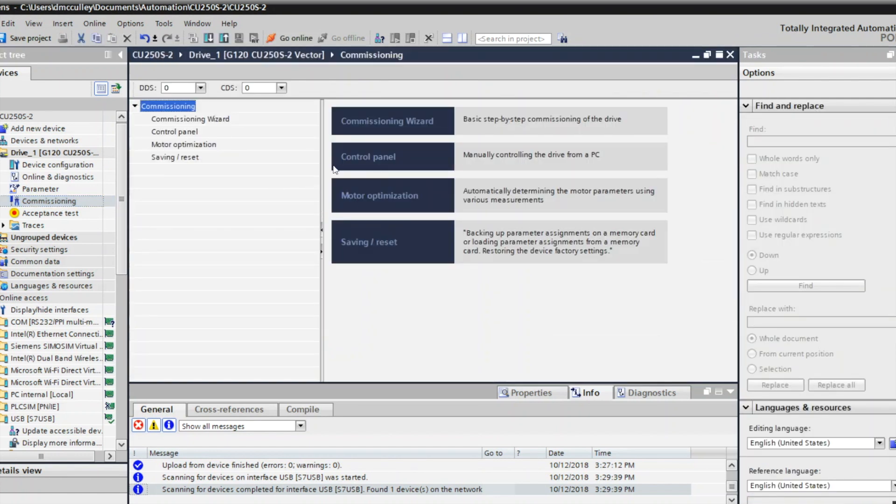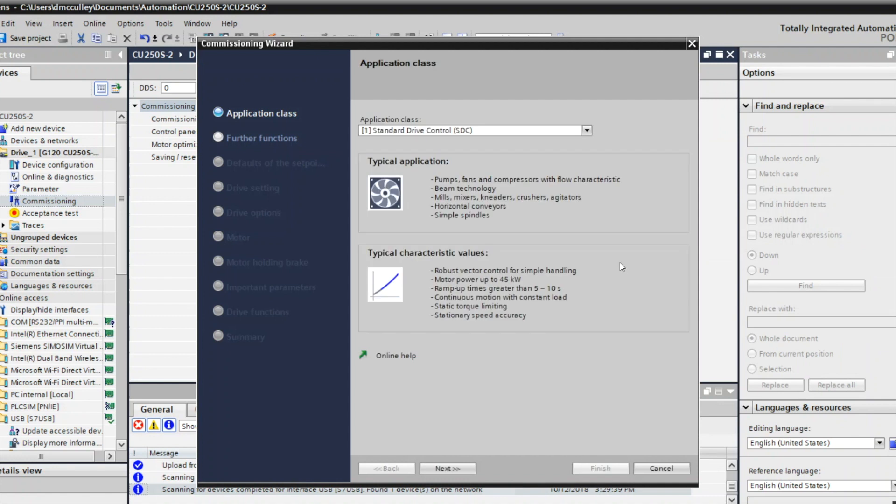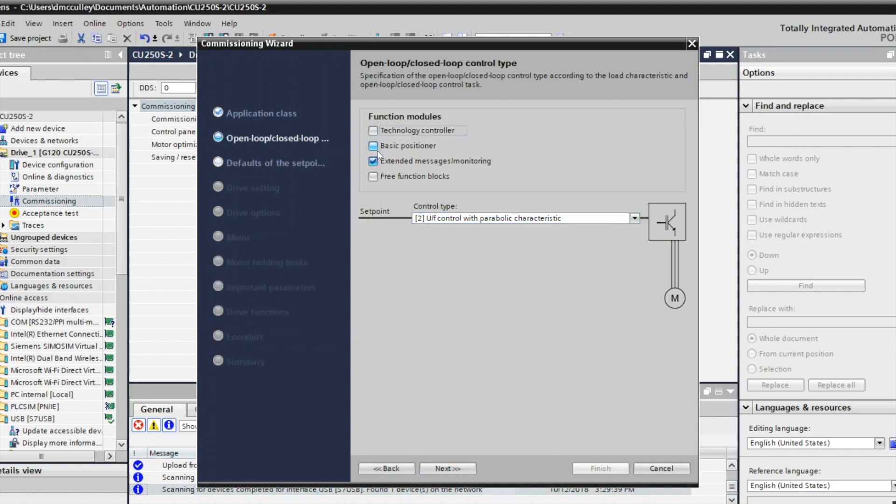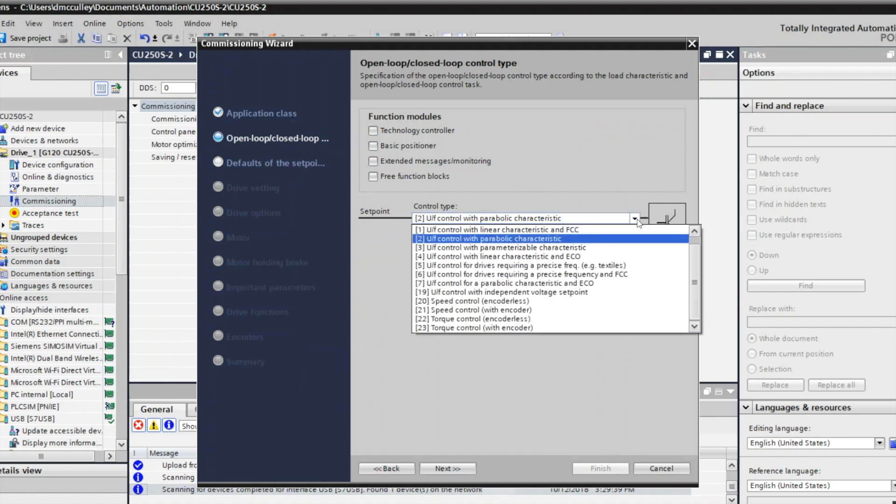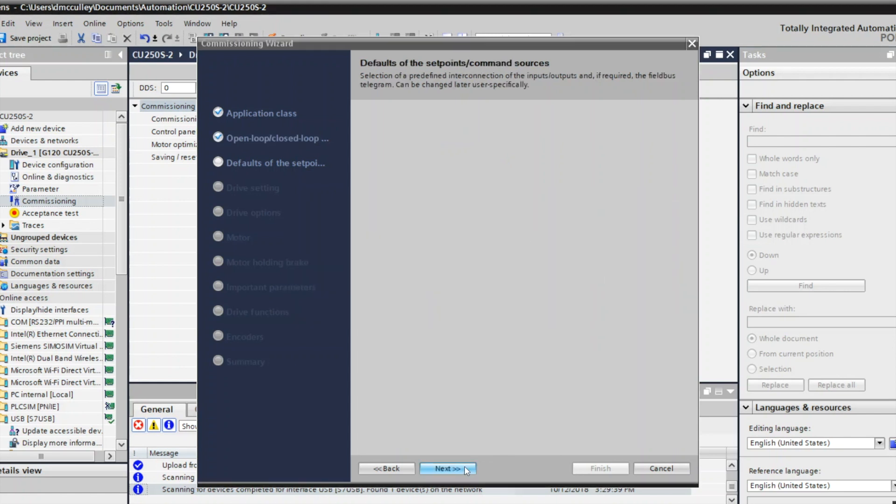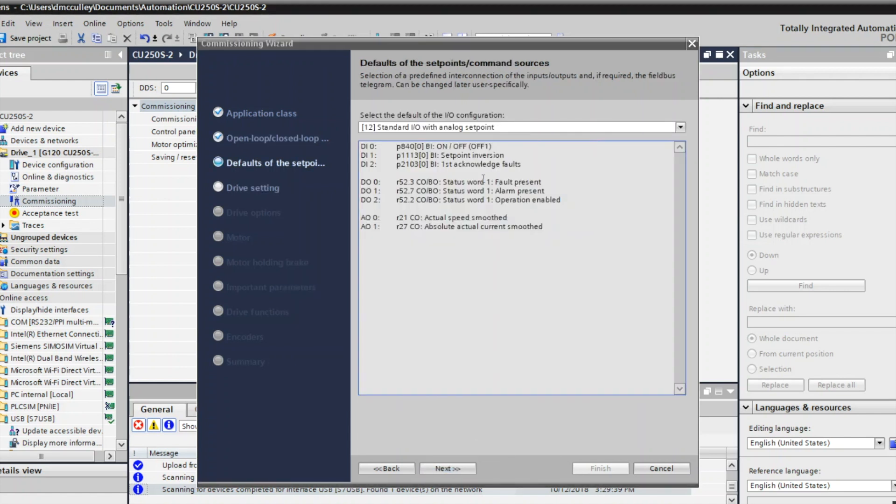I'll go here to commissioning and commissioning wizard. Since I have an encoder, I want to choose expert and next, and then I'm going to uncheck technology and extended messaging because I don't need those. My setpoint type is speed control with encoder. I'm going to use digital inputs and outputs and an analog setpoint, so I'll keep this as my choice for the control.